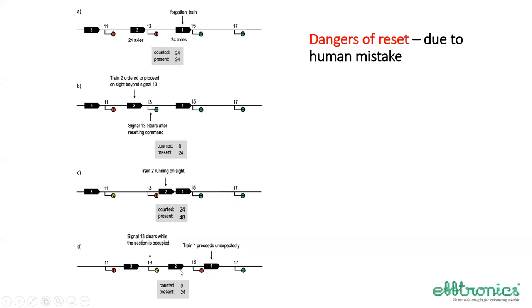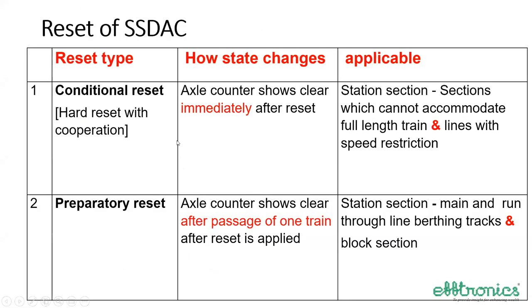Now, with train number 2 in the section, since 24 wheels are out, the count becomes 0. But still there are 24 wheels available belonging to number 2. This has happened because reset was done when the section was still occupied by a train. The counting has become 0. That is why 2 types of resets are provided. One is conditional reset, the other is preparatory reset.